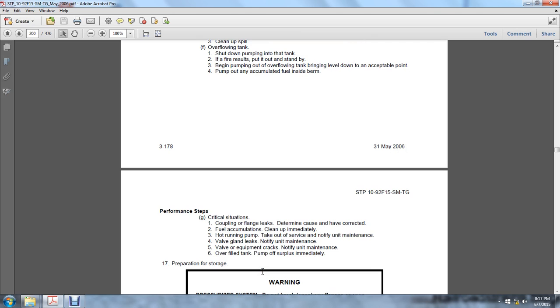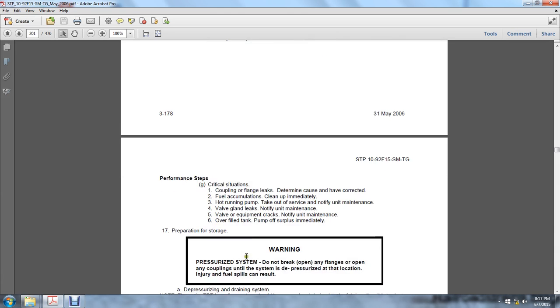G. Critical situations. Coupling flange leaks. Determine the cause, correct it, and clean up fuel accumulations immediately. Hot running pump. Take it out of service and notify unit maintenance. Valve gland leaks. Notify unit maintenance. Valve body cracks. Notify unit maintenance. Overfilled tank. Pump off surplus immediately.